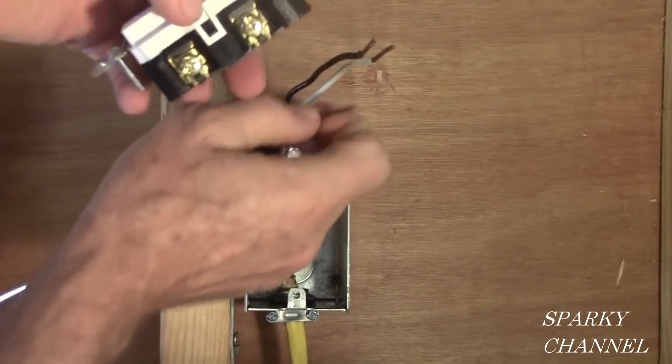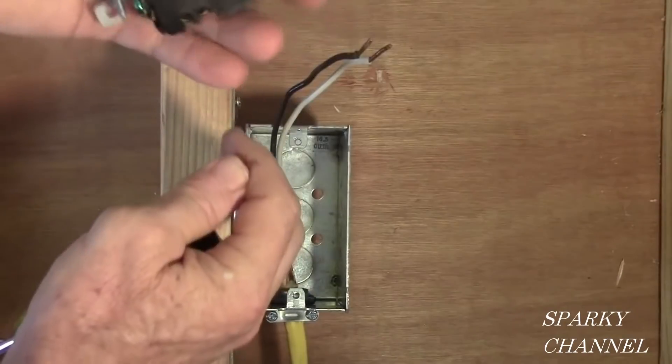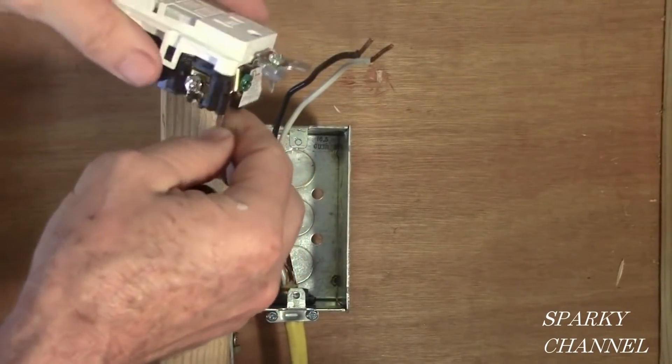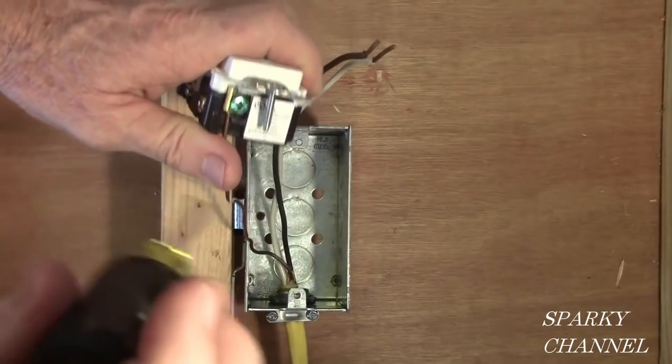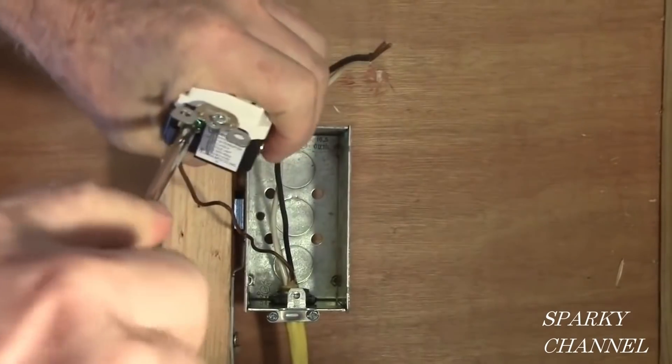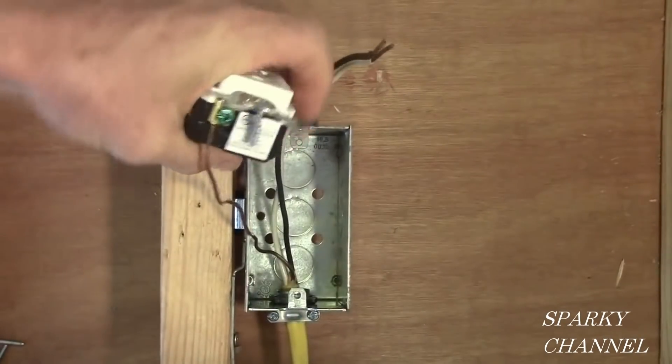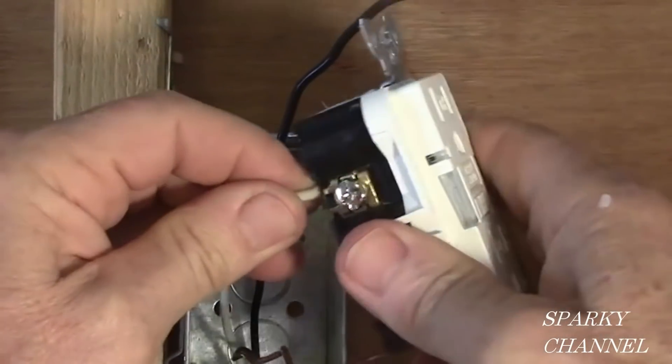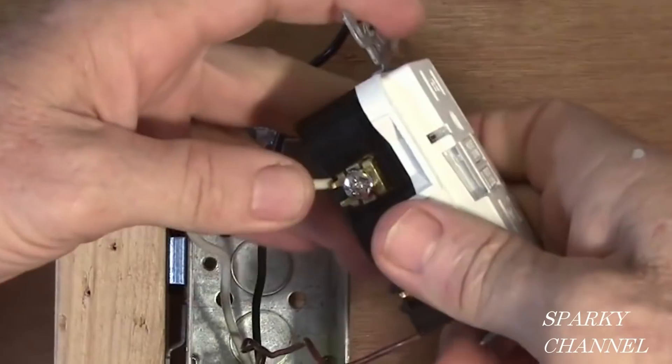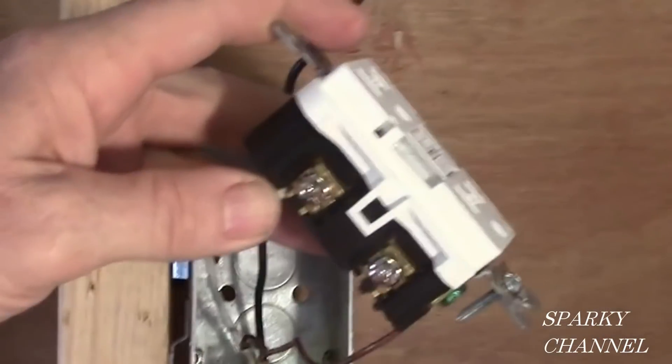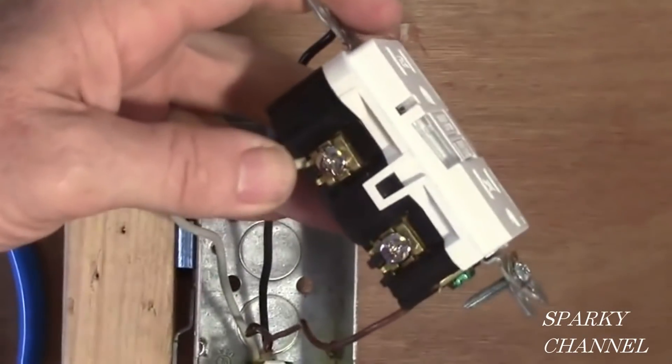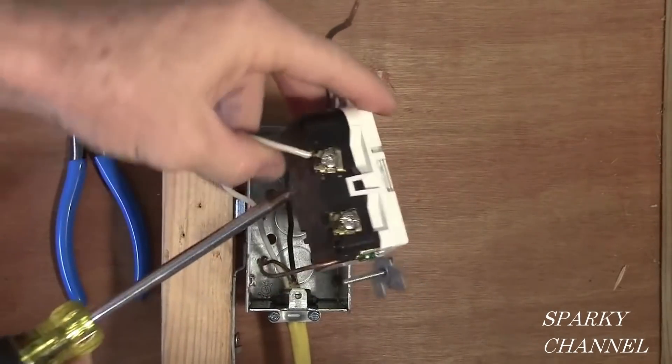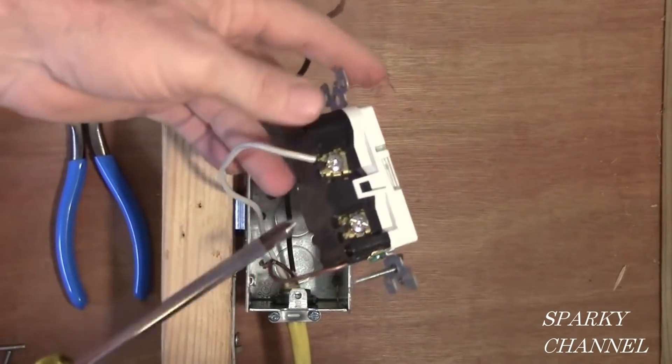So the first thing I'm going to do is take the ground and hook it up. Put it right down here. Okay, it's on real nicely. Next, I'm going to take the neutral and put it underneath the terminal with the silver screw and tighten that down. And this is on the line side of the ground fault circuit interrupter.